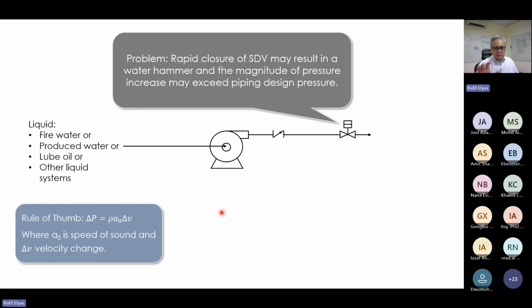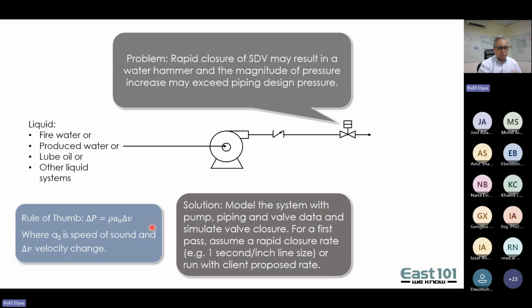Typically, you can use some hand calcs, a rule of thumb, to figure out what kind of pressure increase you're going to have, assuming you have some information on the speed of sound in that particular liquid and the sudden deceleration. A lot of companies have spreadsheets, and I think it's the Joukowsky equation. It'll tell you how fast or slow you need to close a valve, and that gives you a first pass analysis. But later, as your system gets more complex, you might want a proper dynamic hydraulic analysis.